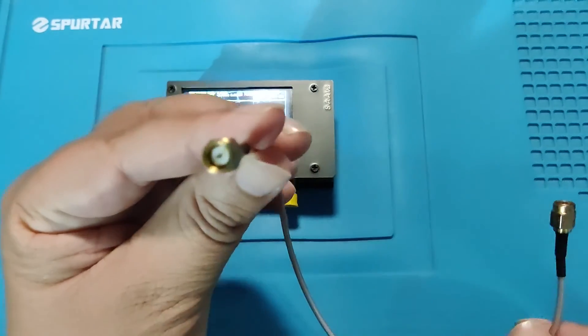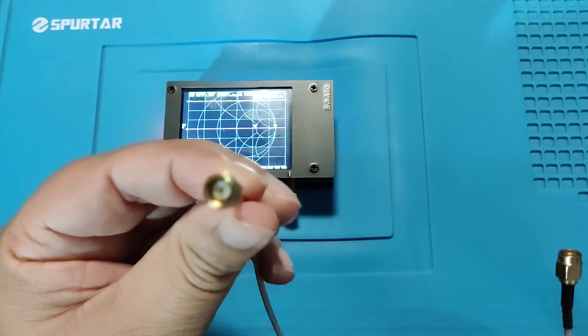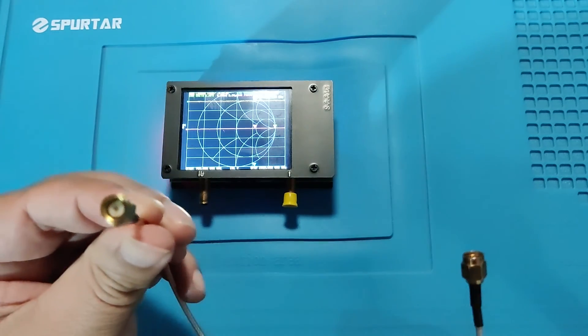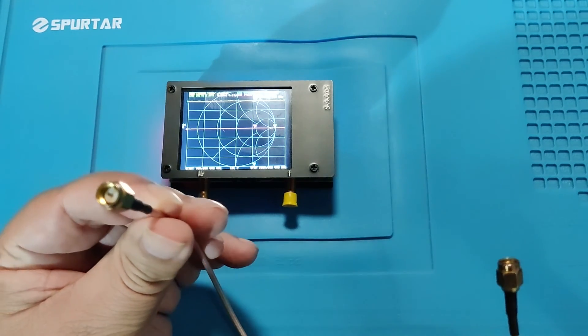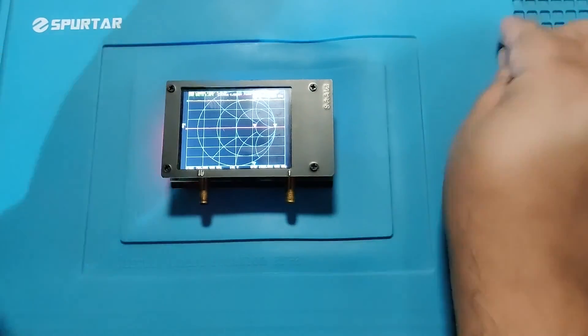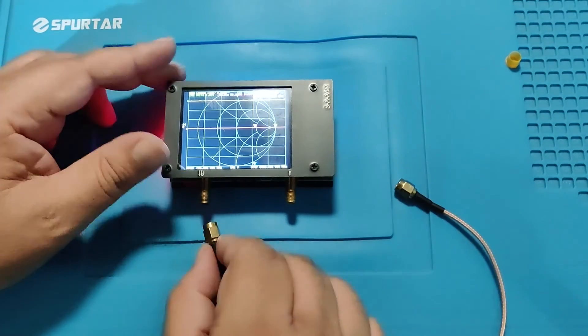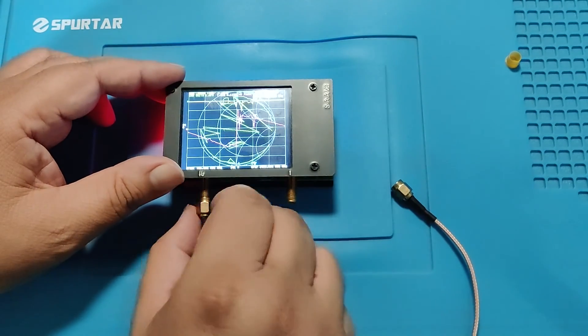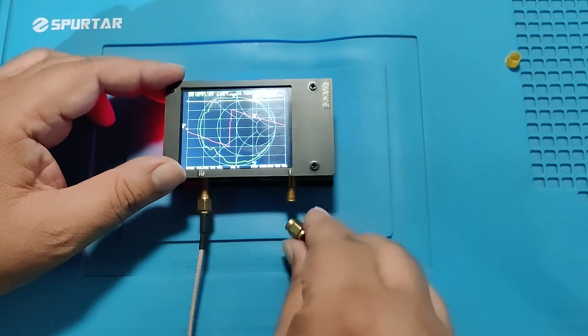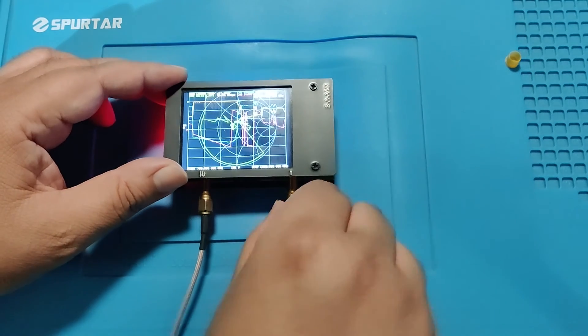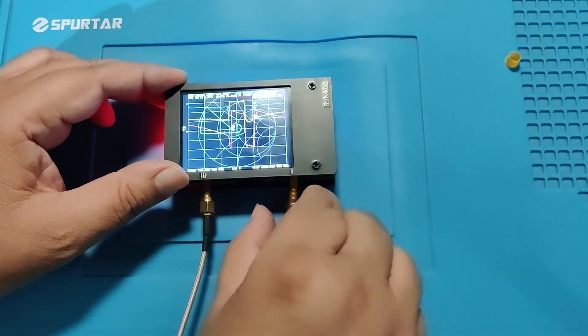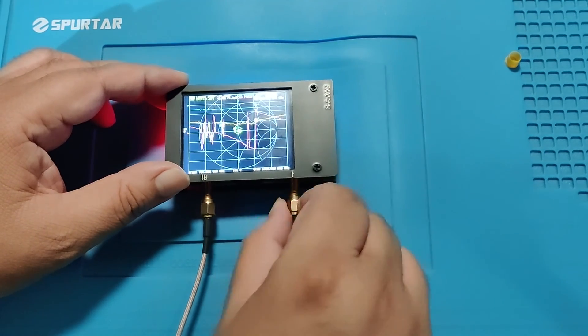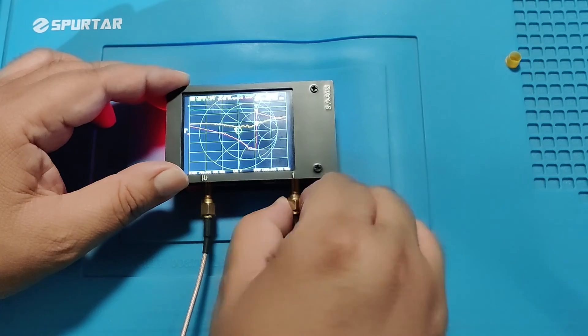For S21 calibration we need this cable with male SMA on both sides. I am removing this dust cover from the S21 port and connecting the S11 port with the S21 port with the help of this jumper cable.